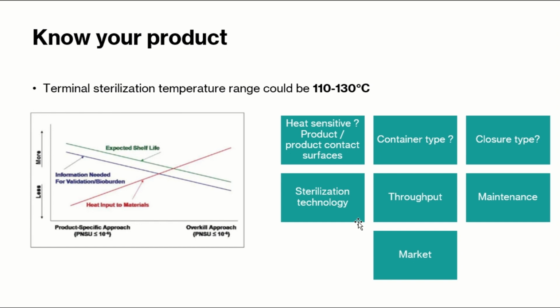But if you have a large volume parenteral, most probably up to 250 ml, you could still use SAM if your product is really stable. But if you are going beyond 250, or 500 ml bags, if it is a bigger one, 1 liter, 2 liter, 5 liter, I would prefer the superheated water technology, because the medium directly touches your product, and the product could be heated up quite faster.